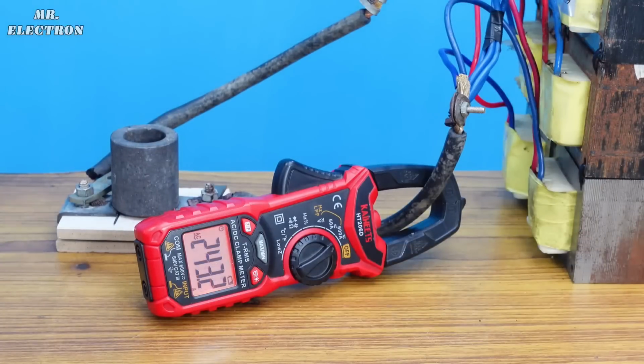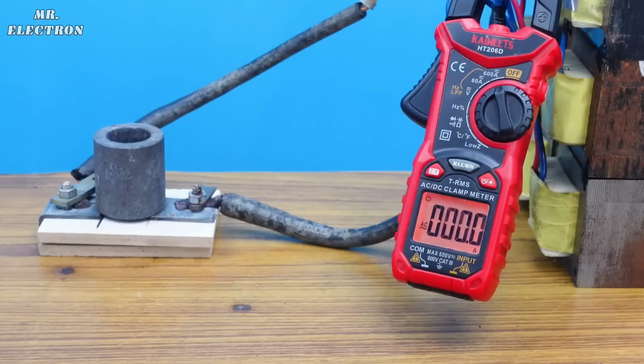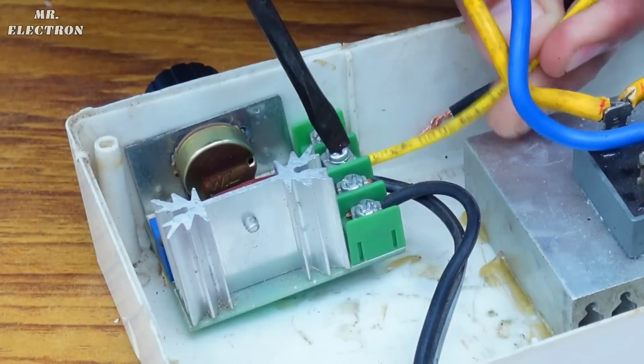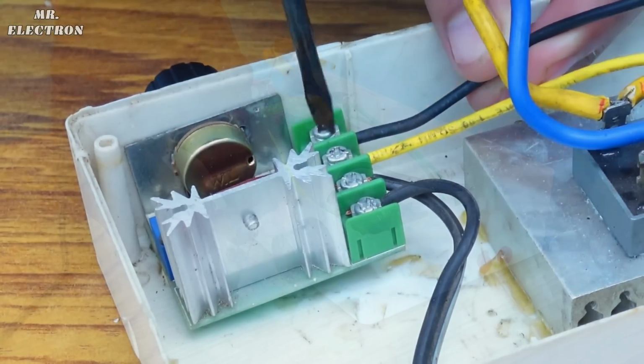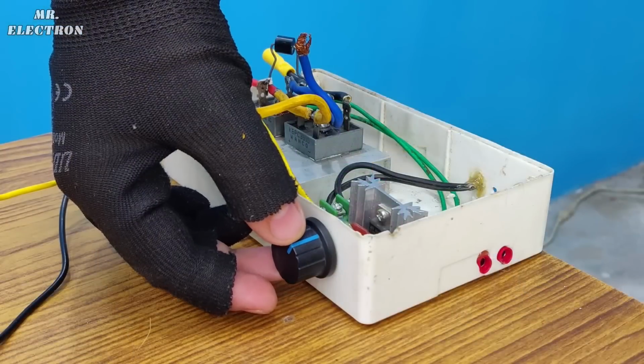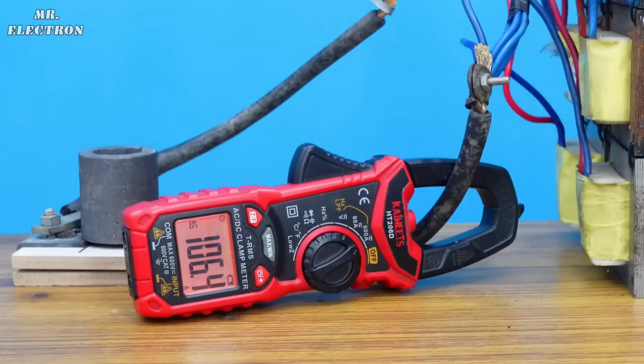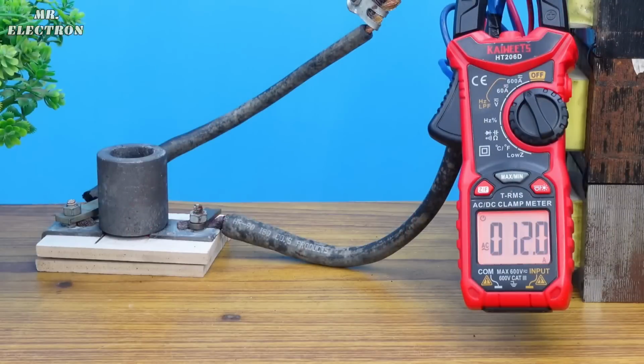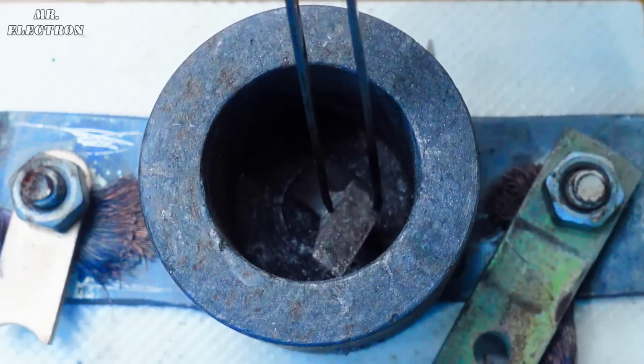It is drawing 245 amperes, with a single transformer current of 40 amps, still high. So now I'm going to use this 2 kilowatt dimmer circuit to reduce the input voltage fed to the transformer, limiting the overall output current to 120 amps, with a single transformer current of only 20 amps or less. This is important for the safety of the transformers.